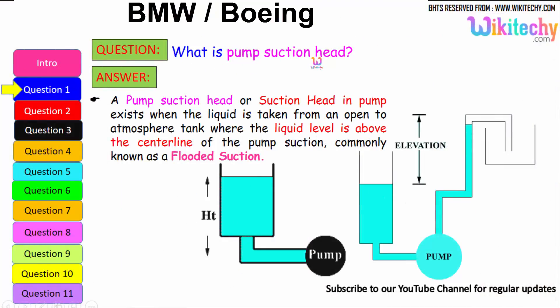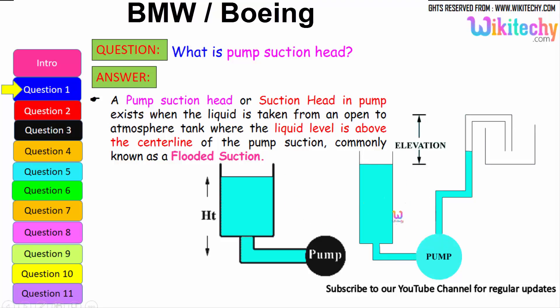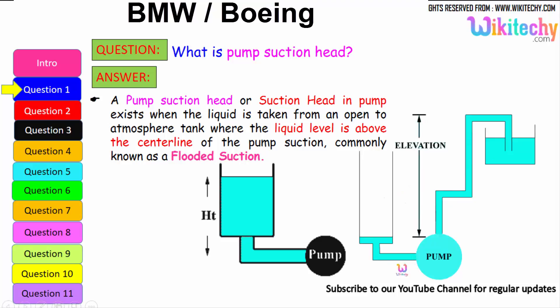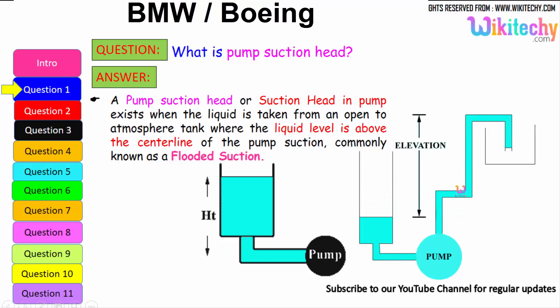What is pump suction head? A pump suction head, or suction head in a pump, exists when the liquid is taken from an open atmospheric tank where the liquid level is above the center line of the pump suction — commonly known as flooded suction. The pump will pick the liquid from one area to another based on atmospheric pressure.